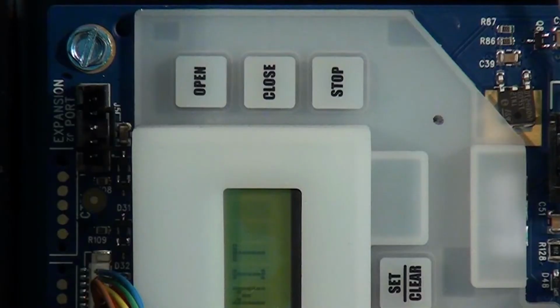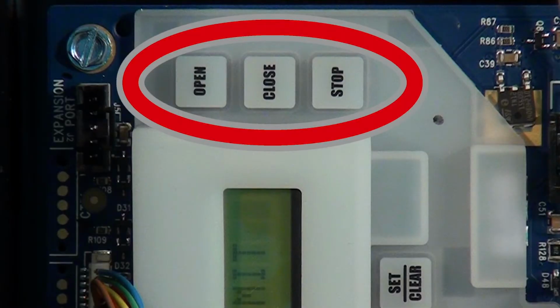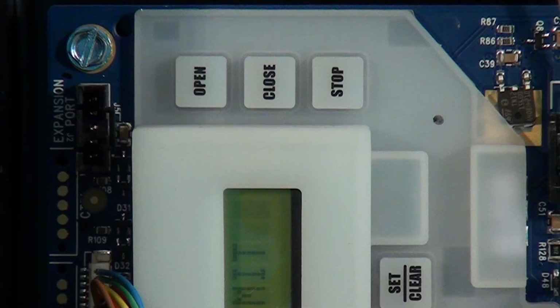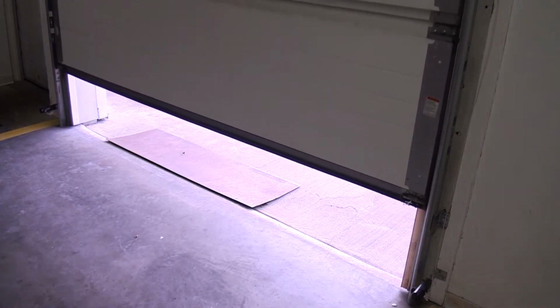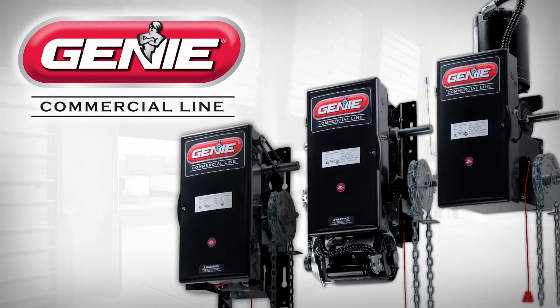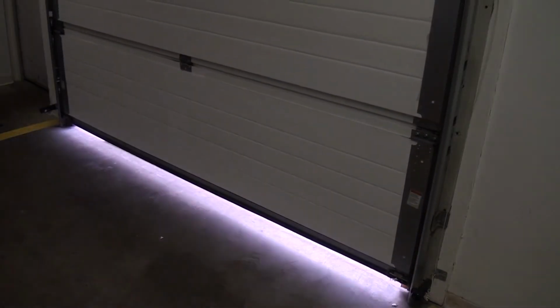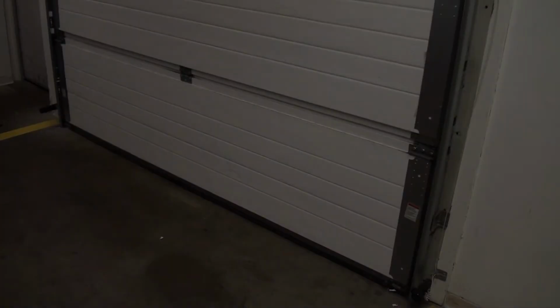Finally, above the LCD display are the open, close, and stop keys, which allow us to operate the door without having to go back and forth to the wall station at each step. Now let's get started. The first step will be to set the operator close direction. The direction of the motor rotation depends on mounting position and how the main input power is wired on three-phase units. This setting is used to set the motor's close direction.